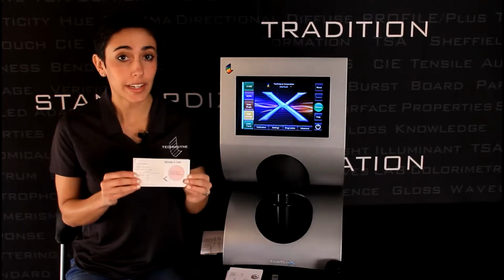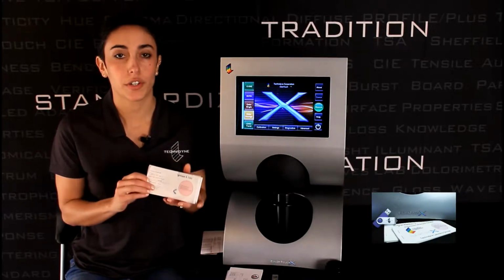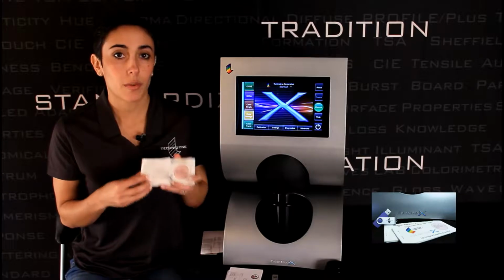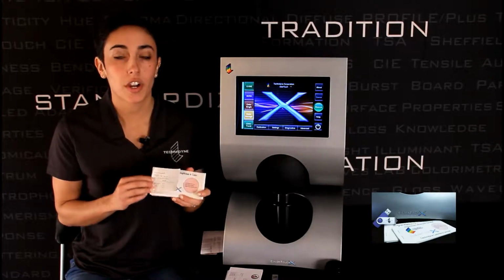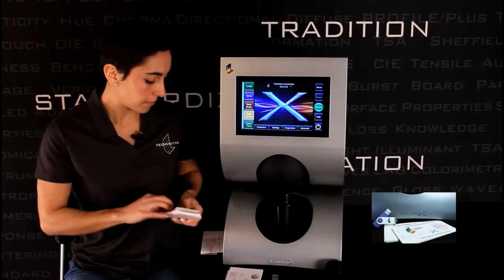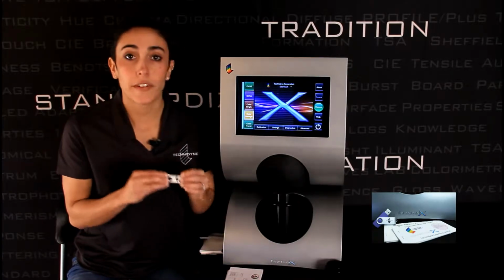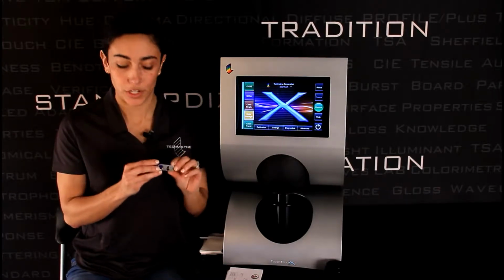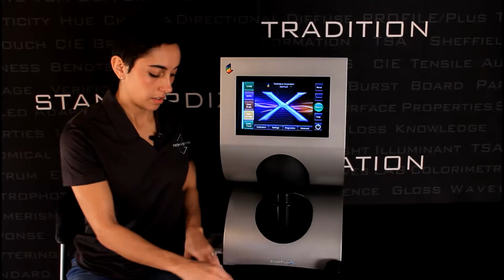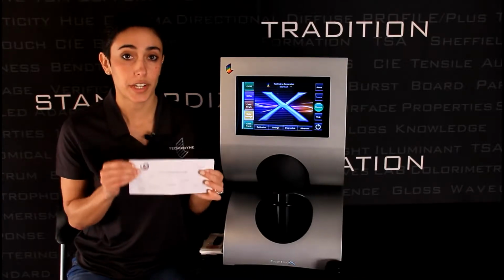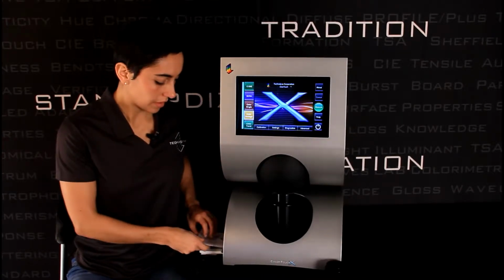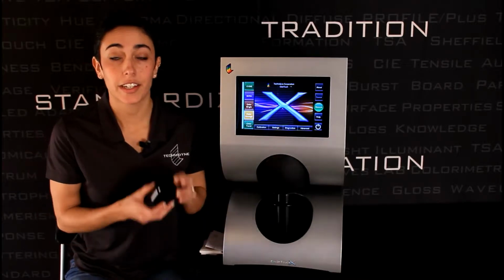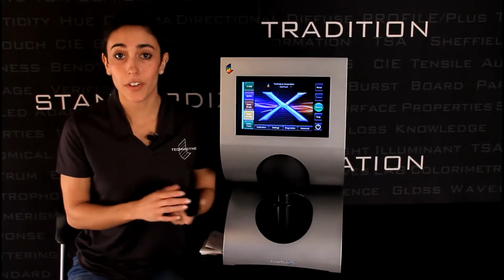The fluorescent whiteness standard and the 90 standard are used for your primary calibration, while the 60 and the 70 standards are used to verify measurement linearity. You'll also find your USB, which holds your calibration data, and you'll find your ColorTouch verification form. The last thing you'll need is your black cup. Once you have all of this together, you're ready to start your calibration.